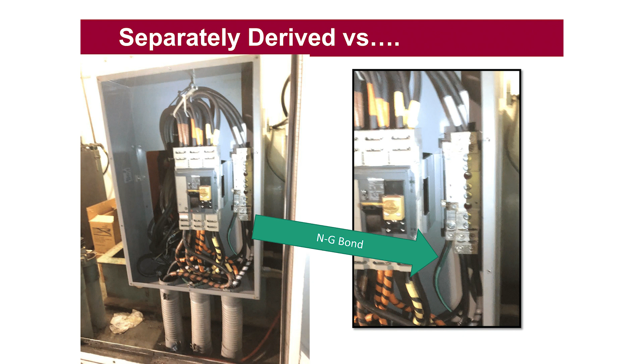When they're bonded, when we have a separately derived system, we bond the neutral and the ground together. So what you have here is the neutral, it's hard to see, but the neutral lugs come in here, there's ground lugs down there, and a bonding jumper that connects the two. That means they're separately derived. We've separately derived the grounding over here, over at the emergency side. Non-separately derived is when you do not have that connection.